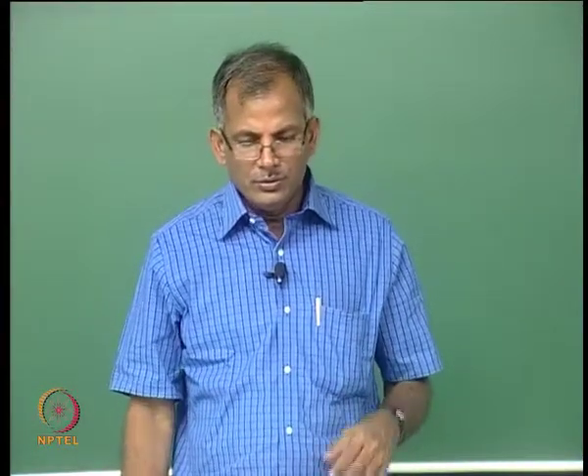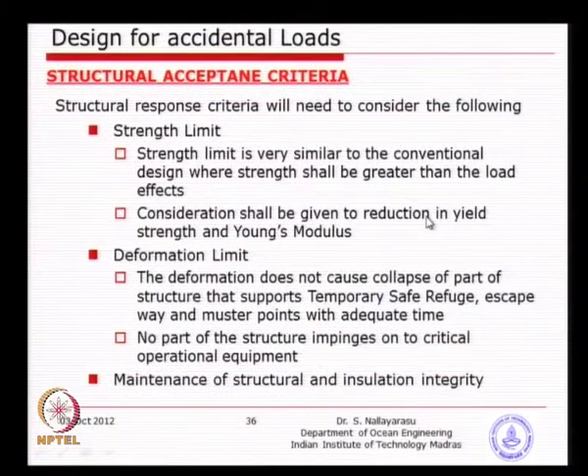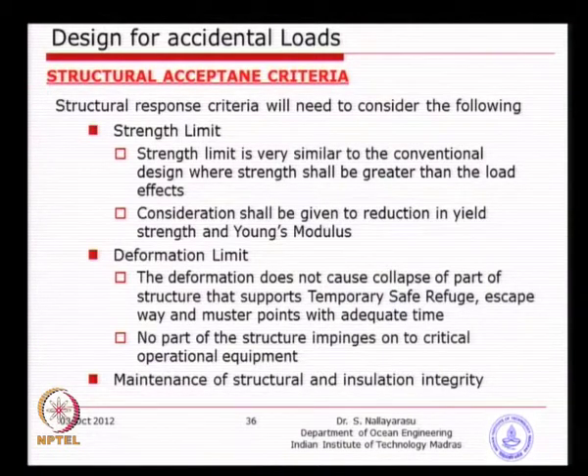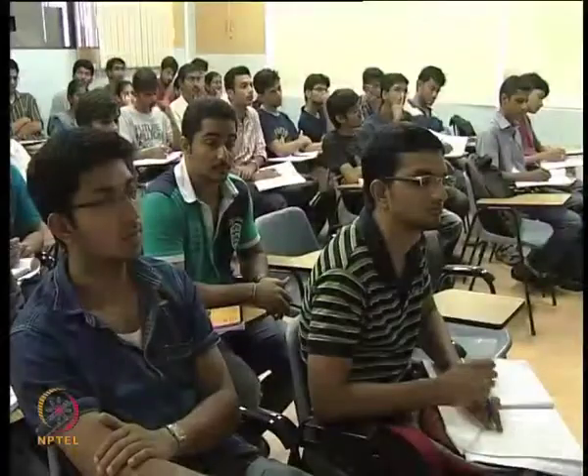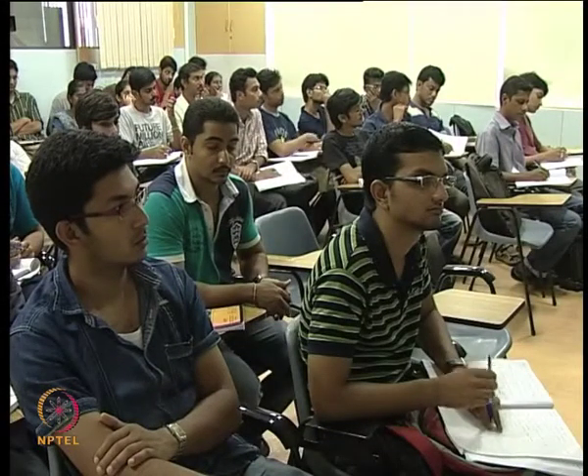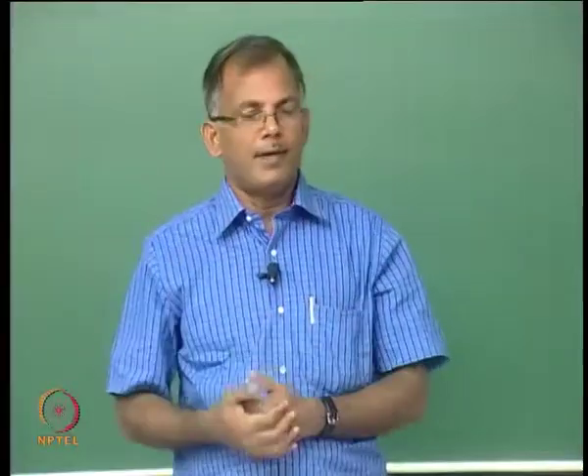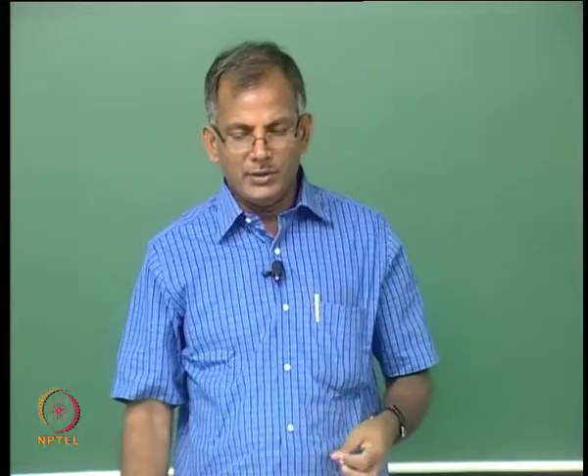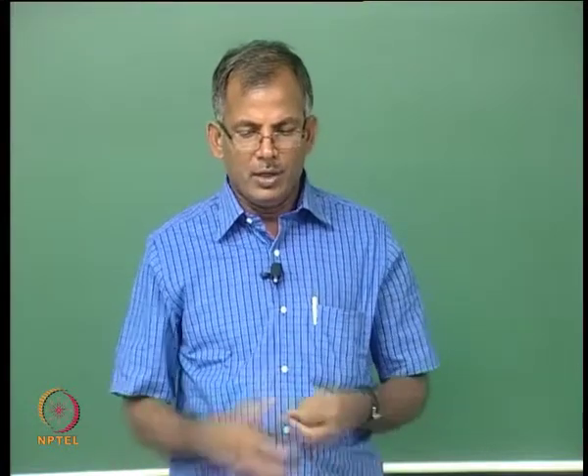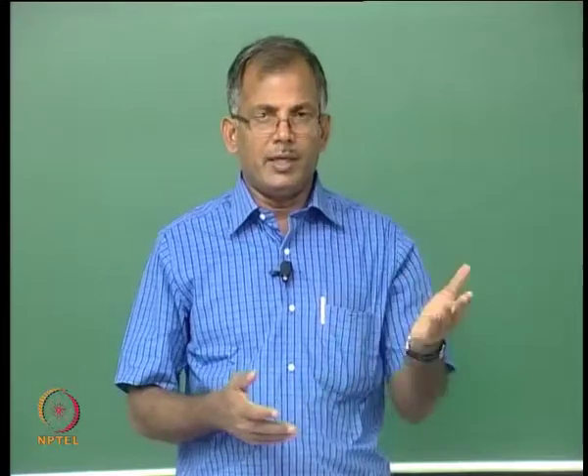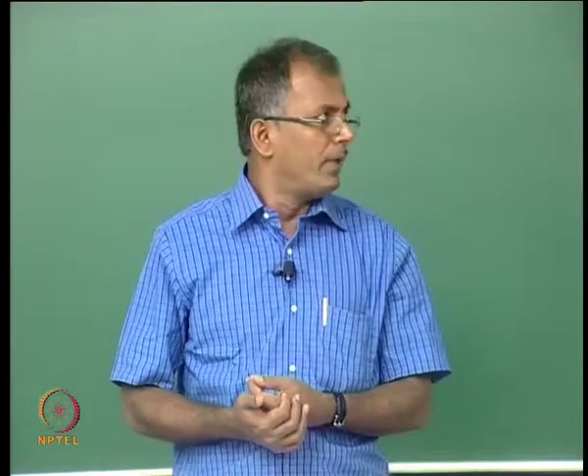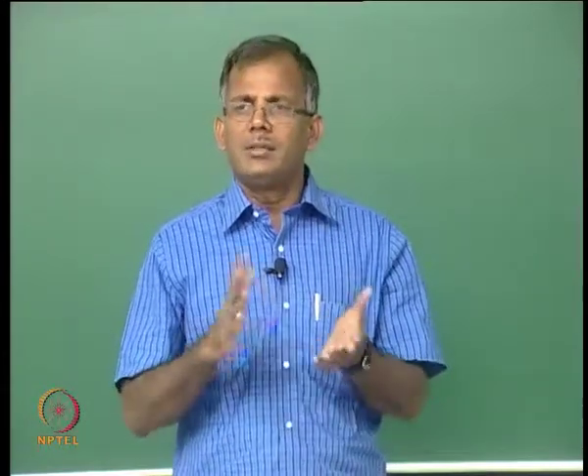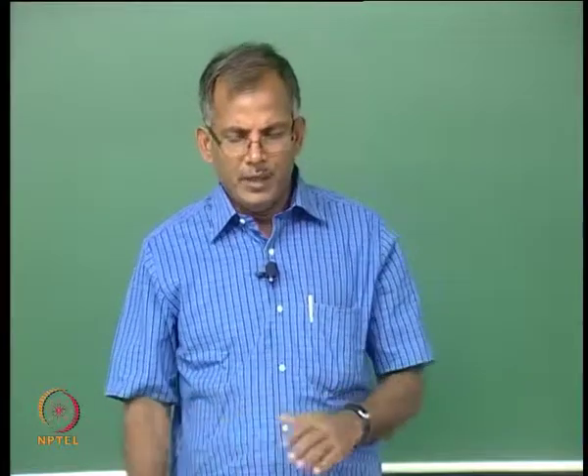Consideration must be given to how steel properties change: how much reduction to yield strength, how much reduction to modulus of elasticity, and the ratio between the two reductions. This is taken from the interim guidance notes — a joint industry project in Europe by several oil companies who made prototype structures for both blast and fire and tested them.